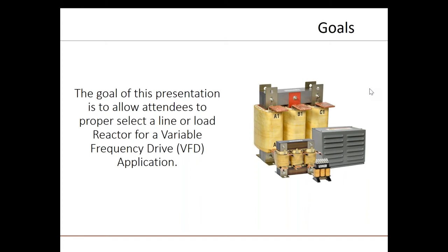VFDs are used to control the speed of an AC motor by simulating different frequencies, and frequency determines motor speed. For the majority of VFD applications, it's easy to size and select a line reactor if you can determine a couple of parameters. This discussion will focus on basic applications involving standard AC induction motors for both variable and constant torque applications, and should be adequate for the vast majority of applications you will experience in the market. If there are any questions, don't hesitate to ask HPS about your application.